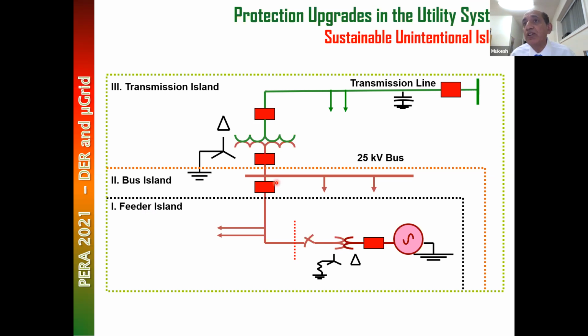Then we say we don't need to worry about any protection upgrades there. All we need to do is microgrid protection now. We don't need to worry about this, because once this opens, it will not sustain as a whole feeder. This microgrid is not viable here, so let's not worry about it. Unless generation is increased, we can connect this distributed resource only in the connected mode. It can only survive in connected mode. It cannot survive in a microgrid, so let's not worry about it. So we don't do any protection upgrades here.